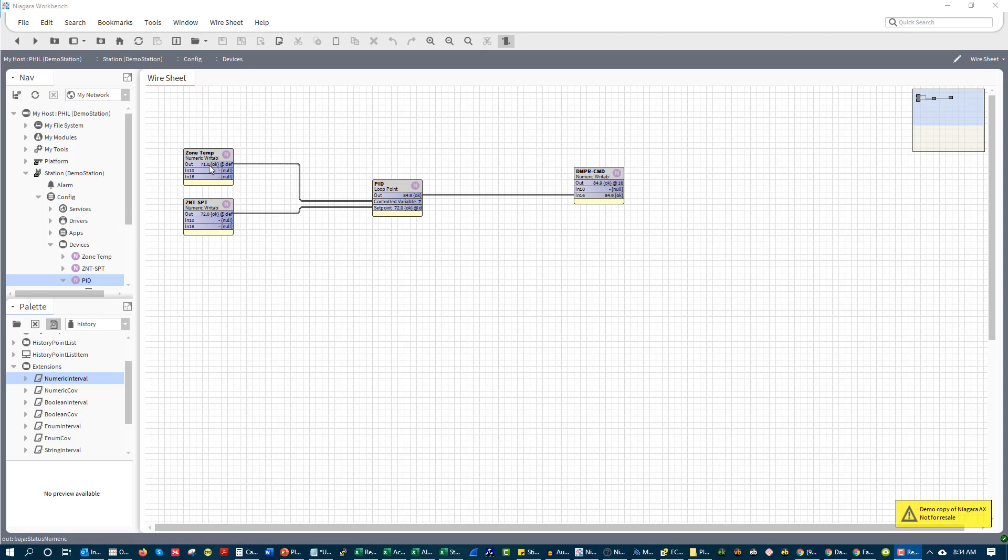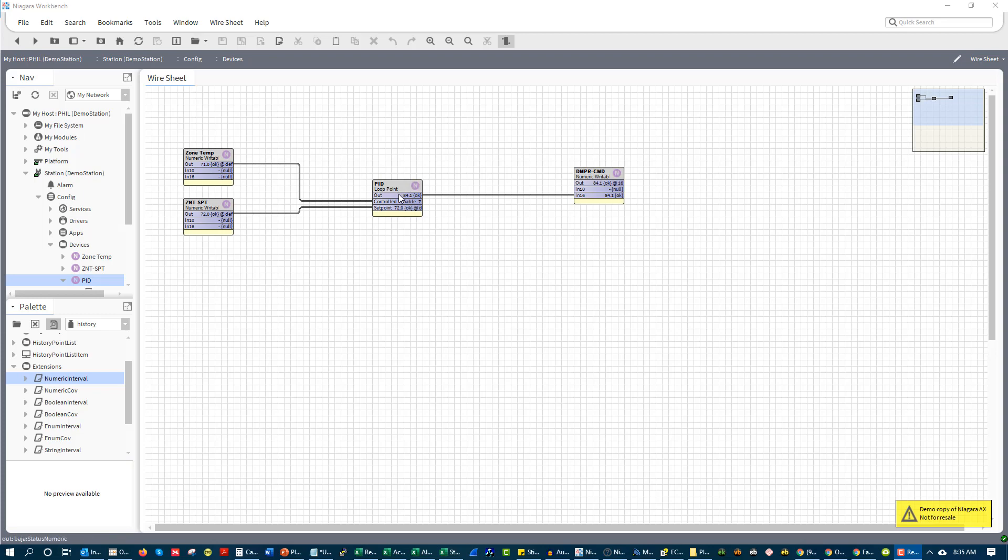So in this loop we can see we have zone temp, we can see we have zone temp setpoint, a PID loop, and a damper command. Now while this isn't actually how we would code it out in the field, this represents this three-point approach to PID loops, which is you have a process variable or input, you have some sort of setting that you're trying to drive that process variable or input to, and you drive it through an output.